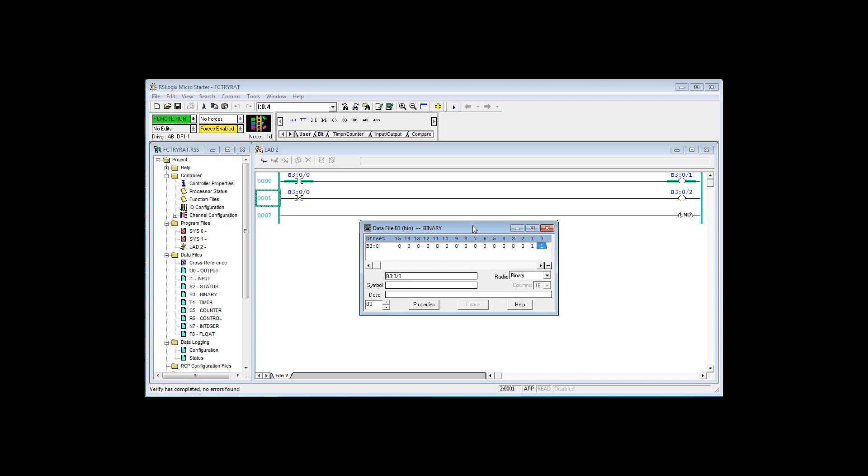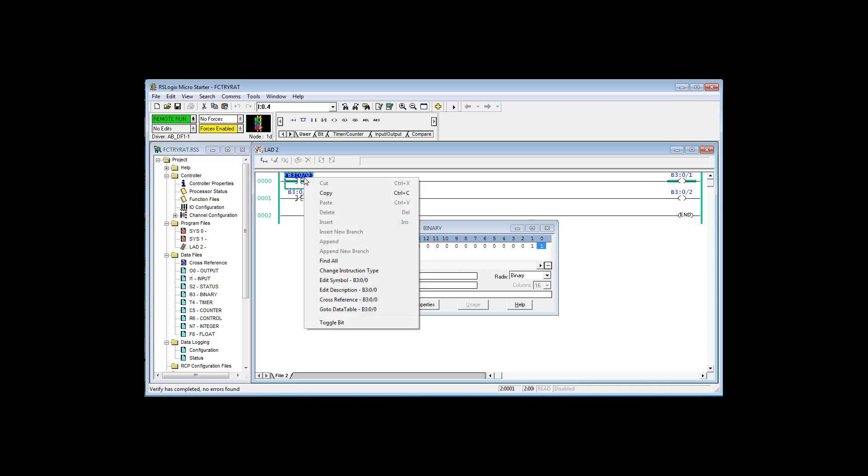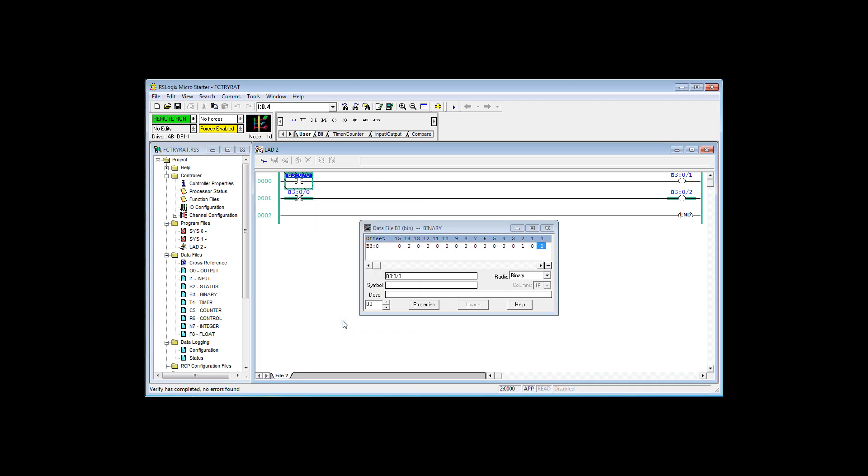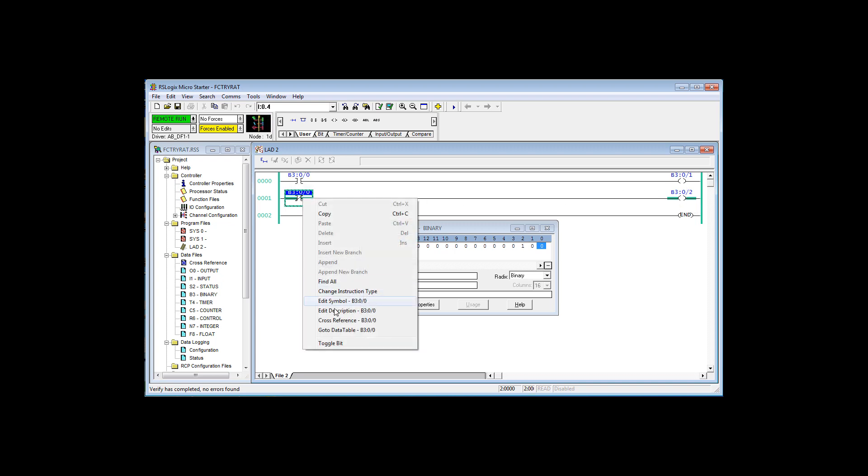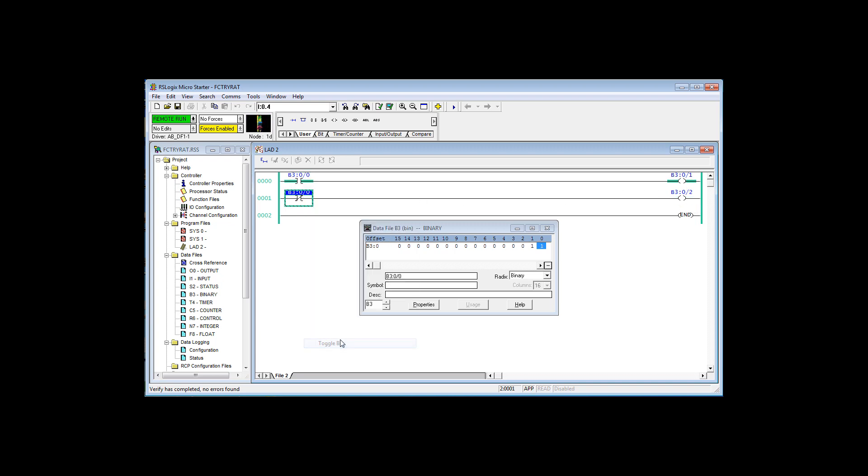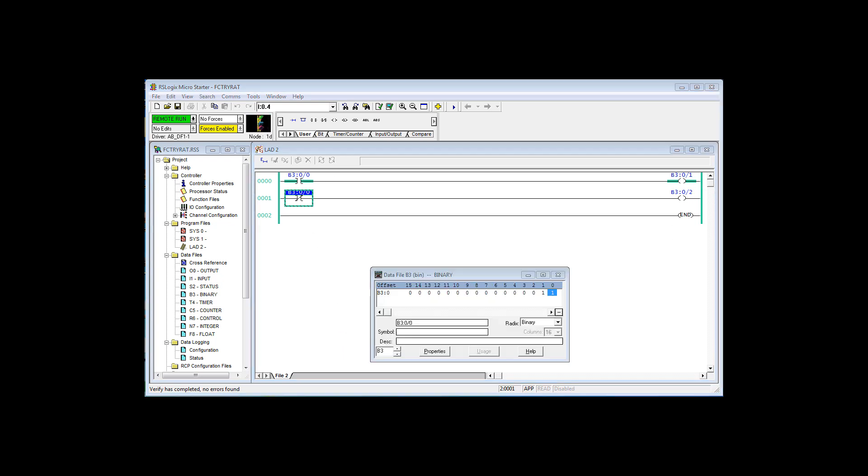Now we have two instructions, a true if on and true if off, reading the same bit in memory, controlling two bits. If I toggle this bit now, watch what happens over here. This instruction is now true because I turned that bit off. True if off, energize output. Toggle it again. True if on, energize output.